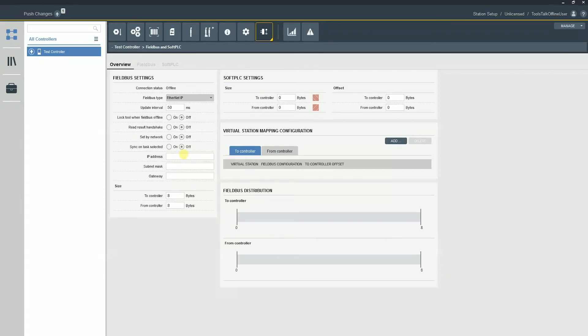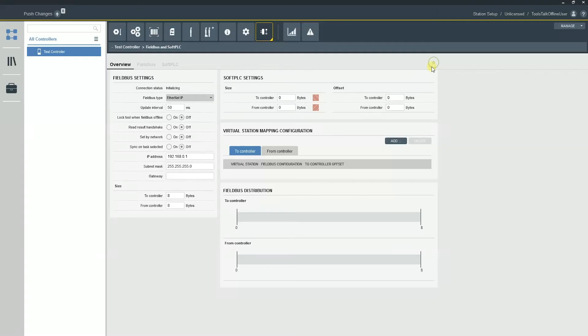Now, I want to talk about the IP address. So we do obviously need to put in an IP address to our PLC. Very, very common mistake. If I put in an IP address and then the customer, for example, says we don't use a gateway, you'll notice something's going to happen. I'm going to push that configuration and you're going to see an unexpected configuration error.